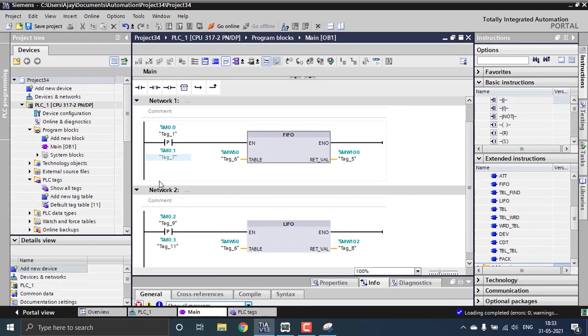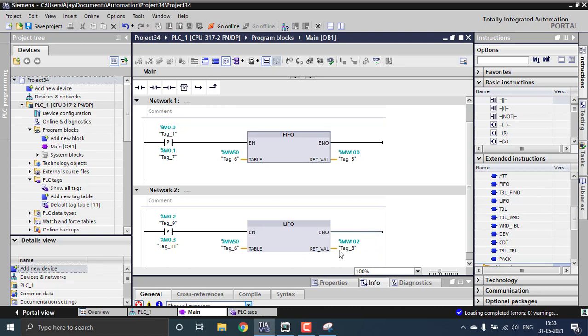Both of the blocks are powered by two memory bits: M0.0 and M0.2. You can see the values inside the table. The FIFO needs a table — FIFO stands for First In First Out. The first filled value should exit on the first triggering. The return value will be MW100 for the FIFO and MW102 for the LIFO. The starting address of the table should be common for both FIFO and LIFO, starting from MW50.